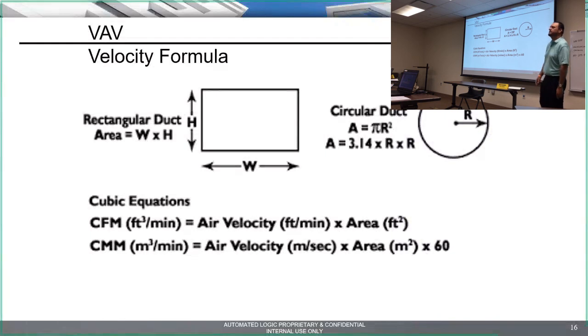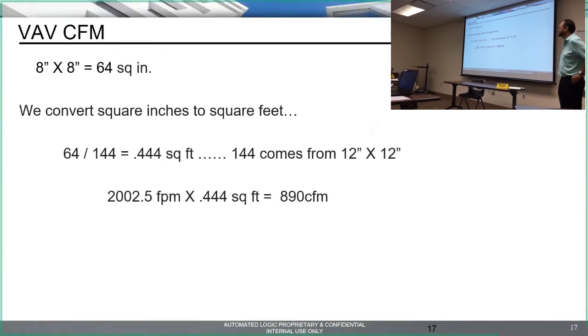Next. So Michael, is it your controller that does that math? Yes. The controller itself is doing all the calculations and everything else. The VAVs that are here, they're Price, I believe. Yes. And they have those sensors already mounted in them? Yep, they came with the sensors already in them. And you mounted the controller to them, was that done in the factory? We shipped the controller to the manufacturer, and Price Industries mounted our controller in the VAV box at the factory, and then they shipped the VAVs to the job site. Okay, so it's factory terminated from the sensors to your controller? Yep. And the controller there is an Automated Logic controller? Yeah, and we'll take a look at one when we get into the graphics. I'll show you a picture of one and how to get to a cut sheet on it and everything.